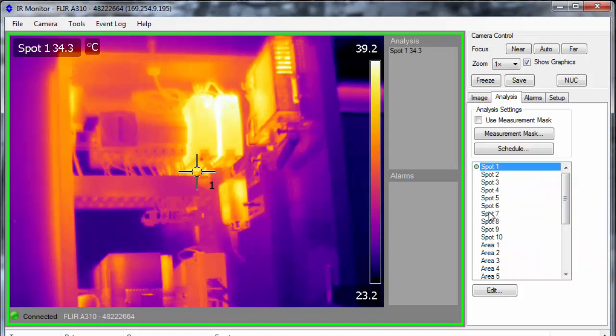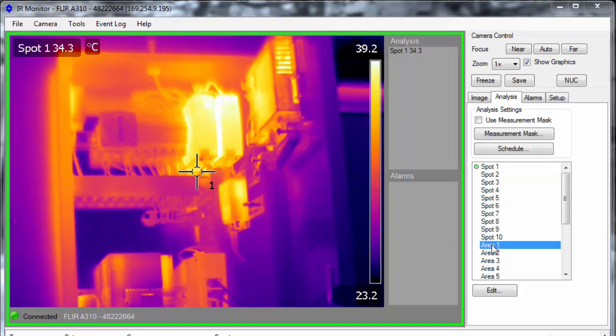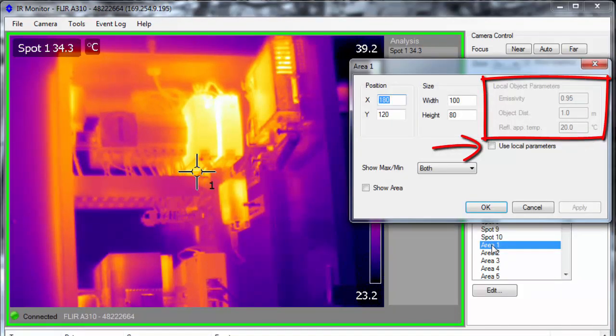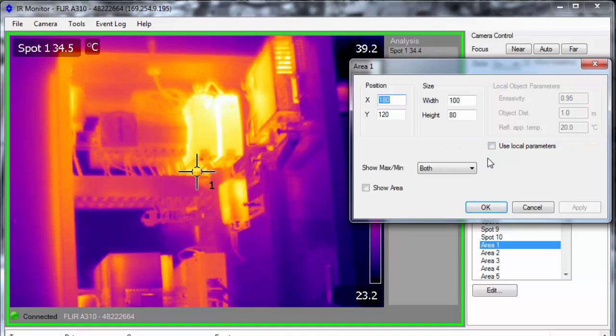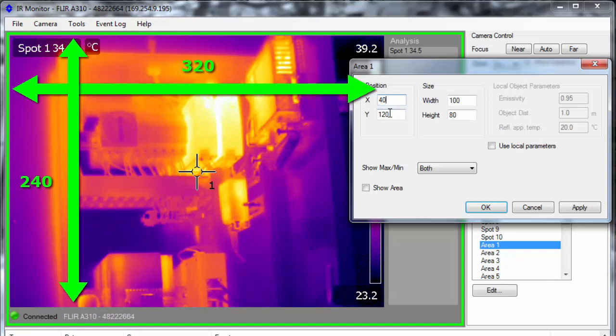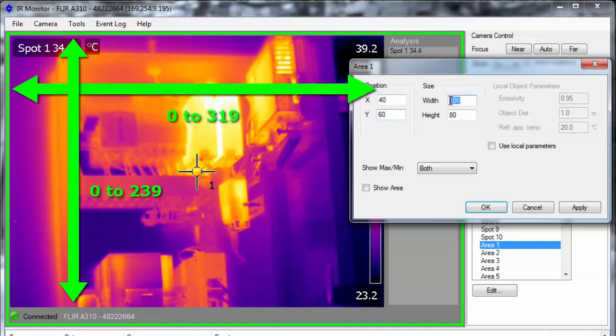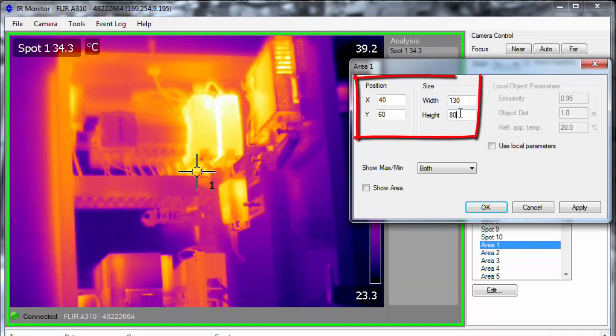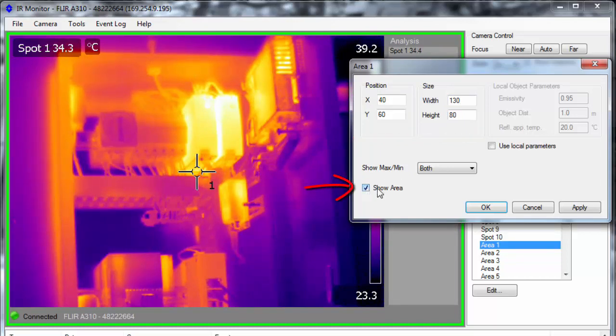To add or edit any measurement tool, just double-click it. Both spots and areas can handle local parameters, in case you want to set different emissivity or distance values for each one of them. The A310 has a 320x240 pixel sensor, so the position coordinates will range from 0 to 319 left to right, and from 0 to 239 top to bottom. Make sure to check the option to show the tool and click OK.